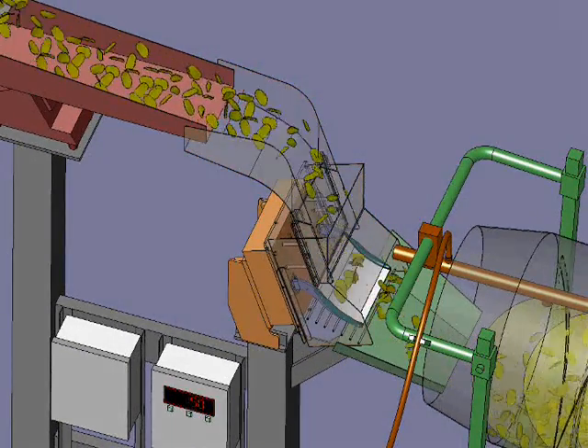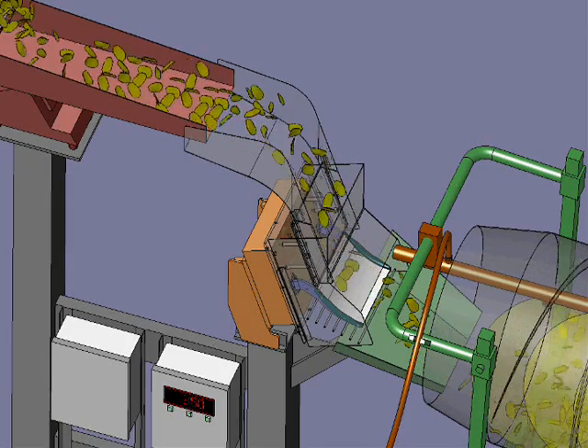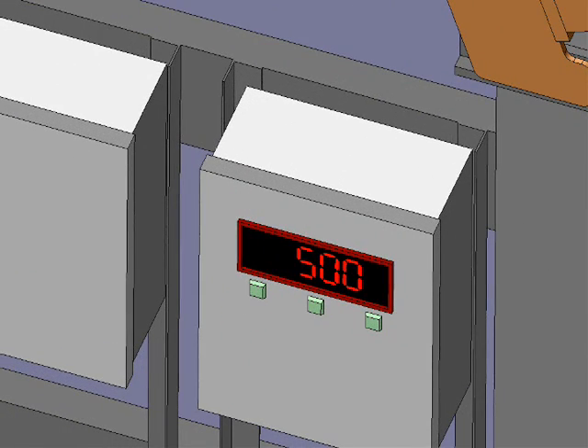The Centriflow Meter is designed for low maintenance with construction of high-grade aluminum. Flow paths are stainless steel. Recalibration is rarely needed because there are no rotating parts, belts, or drives. Electronics are located outside the process stream, which means they are not subject to vibration from the manufacturing process.